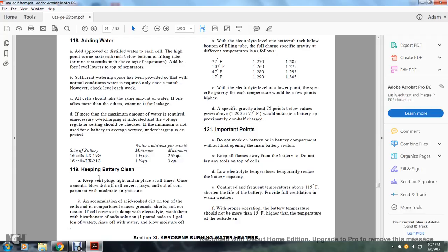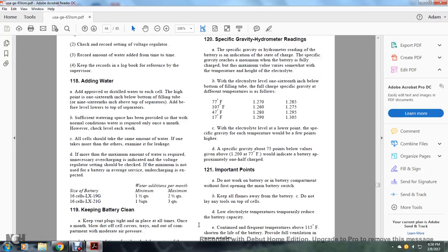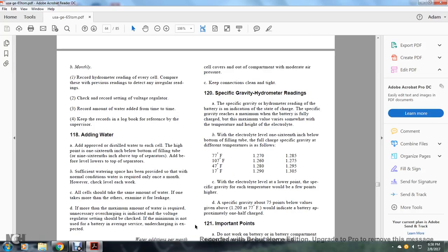Keep vent plugs tight and in place at all times. Once a month, blow out dirt from cell covers and out of the compartment with moderate air pressure. Accumulating acid-soaked dirt on top of cells causes grounds, shorts, and corrosion. Wash cell covers with a bicarbonate soda solution, one pound of soda to one gallon of water. Rinse off with water and blow moisture off cell covers and out of the compartment with moderate air pressure. Keep connections clean and tight.